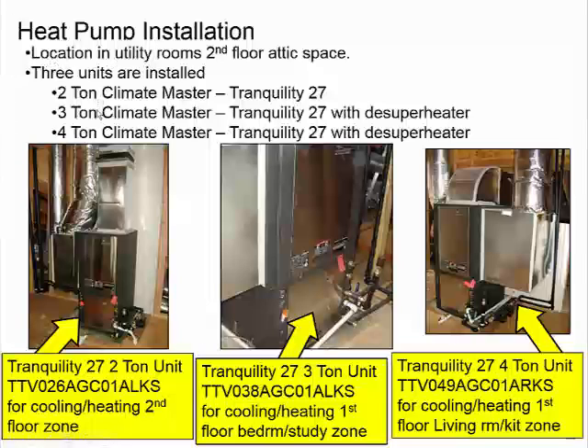This is just showing the installation of those, the Tranquility 27 units, the 2-ton, what it looks like, and the 3-ton, and then the 4-ton. The 2-ton has one pump on the outside of it here, and the 3-ton also has one pump on it. The 4-ton has two pumps on it. I'll show you that a little more in detail in a minute.